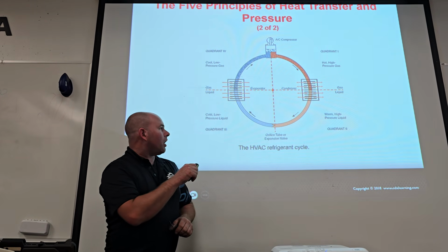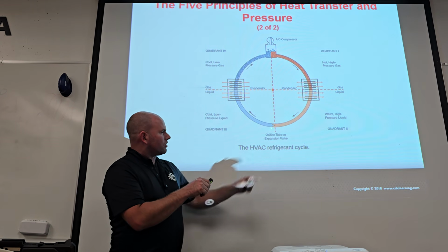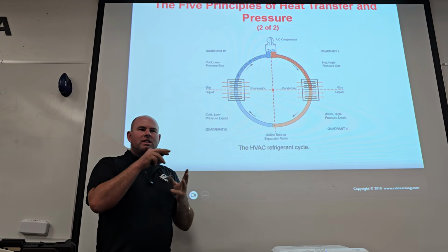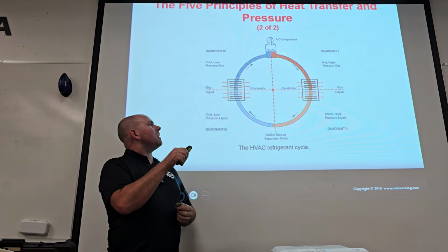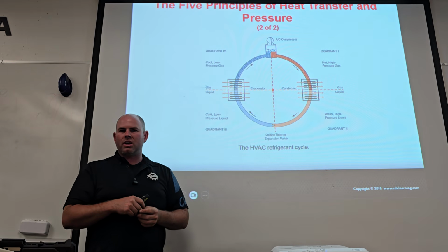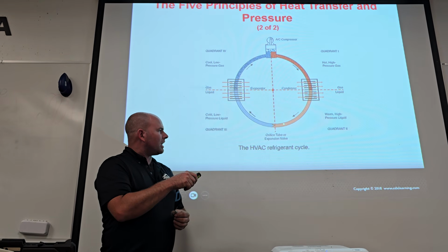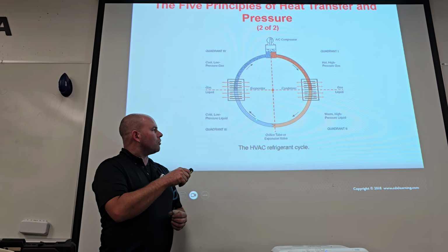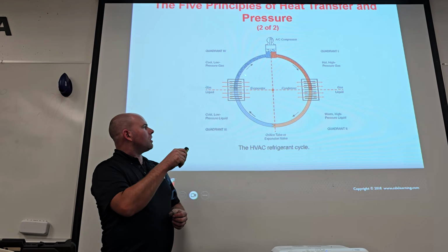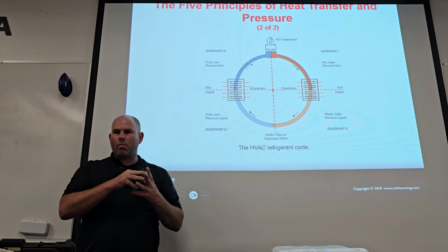So if it was water, we're trying to shove all this water there, but there's only a little pinhole right here. That's what's actually going to build the pressure. The restriction in combination with the pump make the high pressure, and the restriction limiting it, only allowing a little bit of liquid, in this case we'll call it water, through, and the pump trying to draw really hard is actually what's going to make that a low pressure, okay?